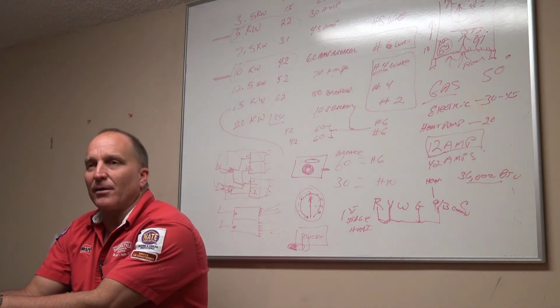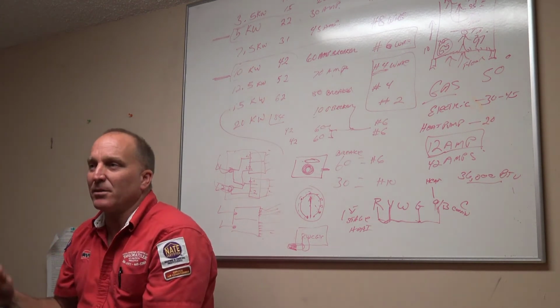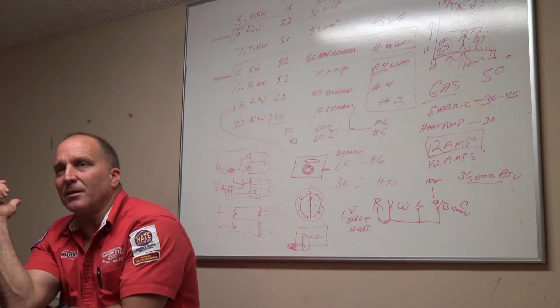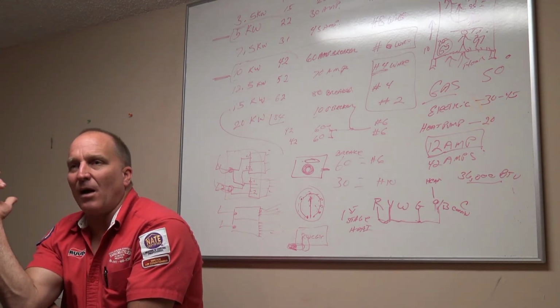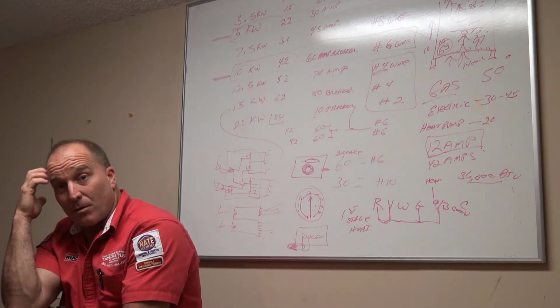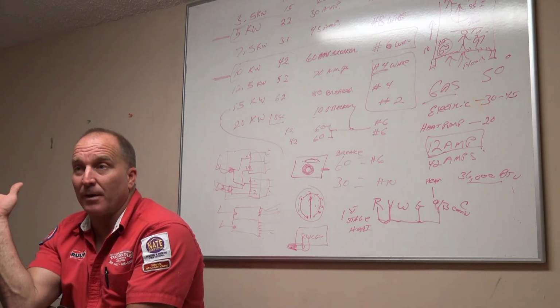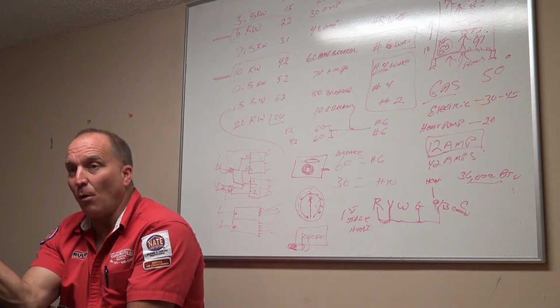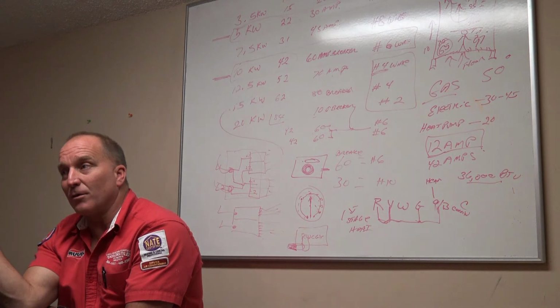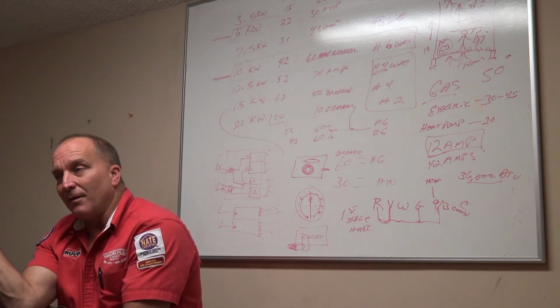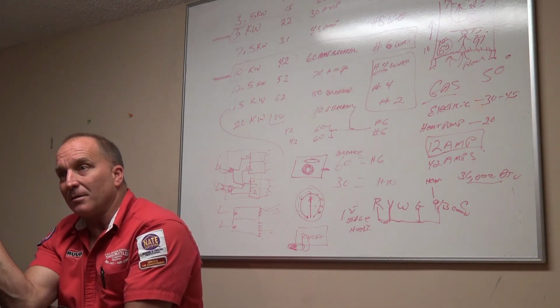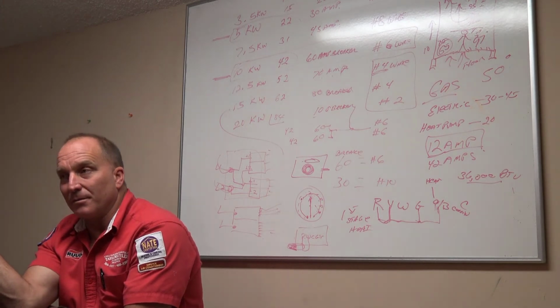So now the customer calls back and goes, Cousin Bill said you screwed me out of $500. That system wasn't low on refrigerant. I want my $500 back. I go, no ma'am, we're not giving you $500 back. Here's a picture of your system before, when I got there. Here's a picture of your system when I left. And I can prove that it is correct pressures and temperatures.